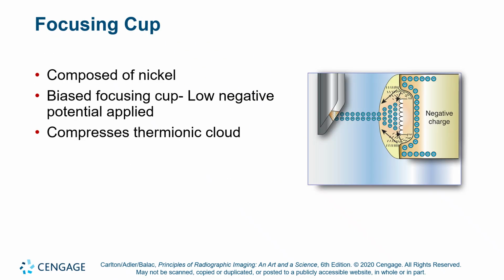So here's a good diagram of the focusing cup. Focusing cup, again, is for optimal efficiency. It's not necessary. You could totally build an X-ray tube without a focusing cup. Just have a bare piece of coiled wire sticking out there into the middle of the tube. But that means your electron cloud is not going to be impeded and confined to a small space. And so we're getting repulsive forces from the focusing cup that keep the excited electrons down in the bathtub. It's only when we apply the high voltage that the electrons respond to an even greater force and accelerate across the tube. They're confined by the focusing cup until the high voltage generator and the exposure switch is turned on.